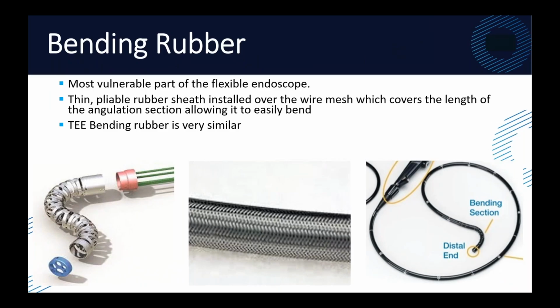So here's an up close and personal look at the bending rubber section. This happens to be on an endoscope, but I can tell you it's almost identical when it comes to TE probes. The only thing that might be a little bit different is the actual wire mesh articulation section that's on the left side of the image there. But when you have this bending rubber, you have this articulation section, and that is there first. Then it is covered with this chainmail section.